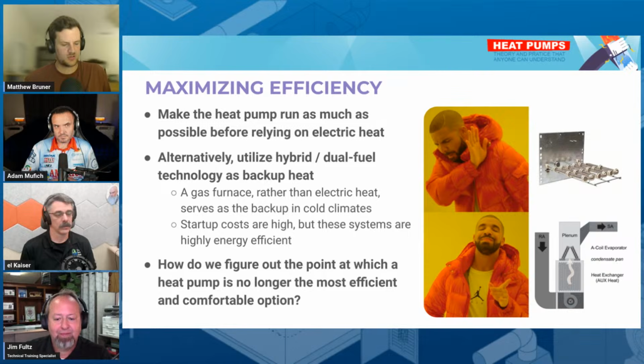So one thing I wasn't quite clear on is, do the controls turn on the auxiliary heat and then turn it back off before it reaches set point? So they allow the heat pump to just keep maintaining. They just help bump it back up and then shut off and it keeps running. Okay. Yeah, cool. It's basically a down staging. So it keeps the first stage on, which would be the heat pump, and then it cycles on that second stage and cycles it back off.